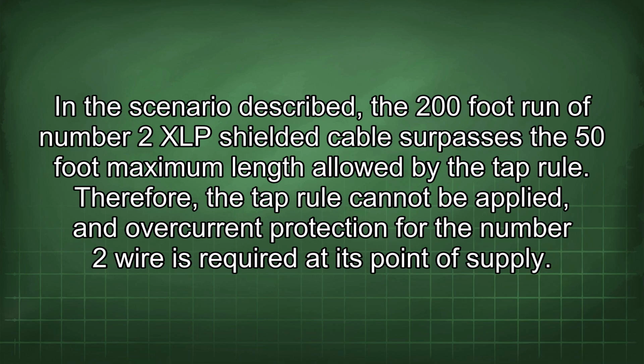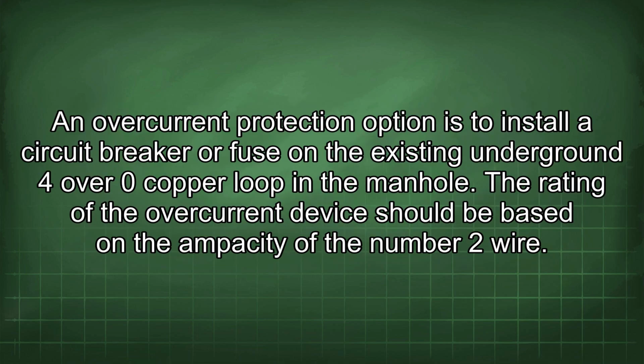In the scenario described, the 200-foot run of number 2 XLP shielded cable surpasses the 50-foot maximum length allowed by the tap rule. Therefore, the tap rule cannot be applied, and overcurrent protection for the number 2 wire is required at its point of supply. An overcurrent protection option is to install a circuit breaker or fuse on the existing underground 4/0 copper loop in the manhole. The rating of the overcurrent device should be based on the ampacity of the number 2 wire.